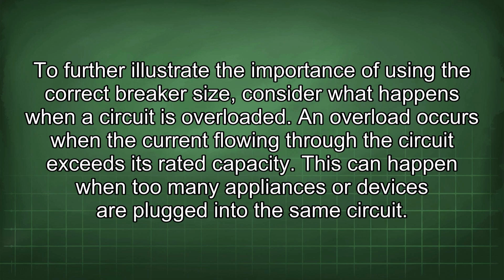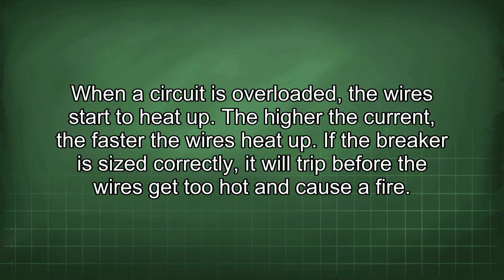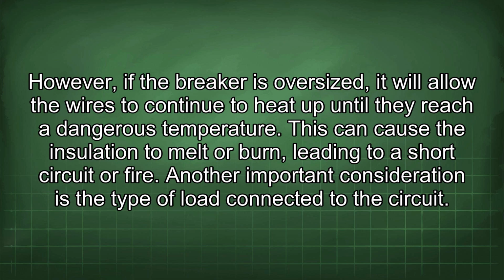This can happen when too many appliances or devices are plugged into the same circuit. When a circuit is overloaded, the wires start to heat up. The higher the current, the faster the wires heat up. If the breaker is sized correctly, it will trip before the wires get too hot and cause a fire. However, if the breaker is oversized, it will allow the wires to continue to heat up until they reach a dangerous temperature. This can cause the insulation to melt or burn, leading to a short circuit or fire.